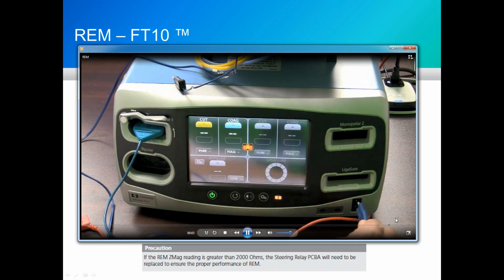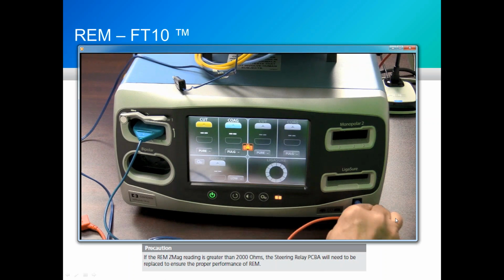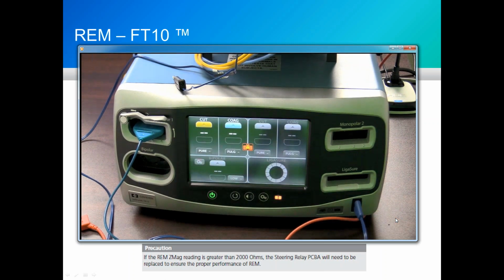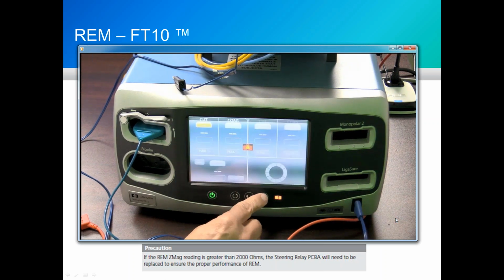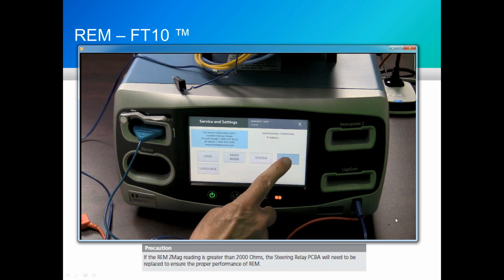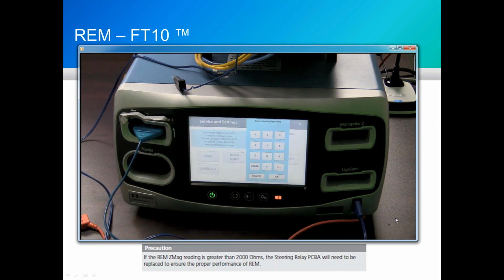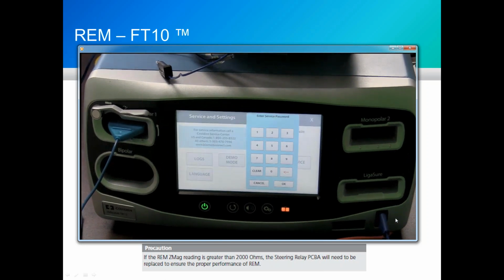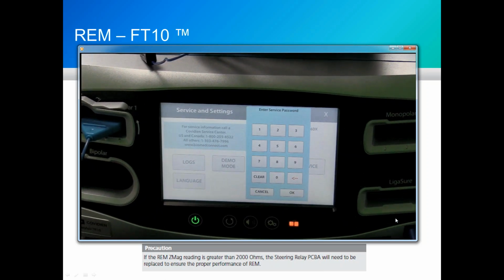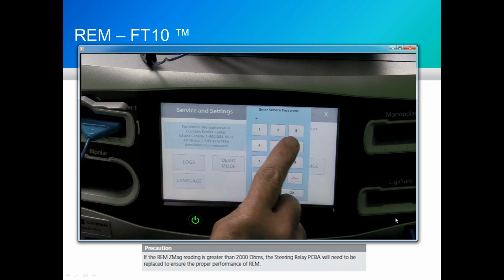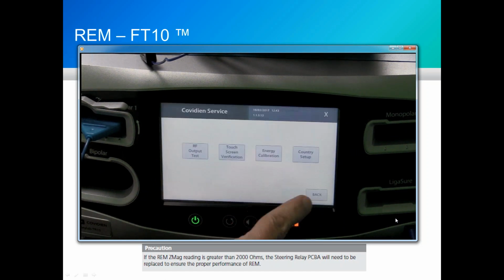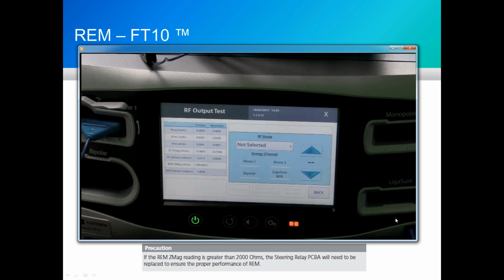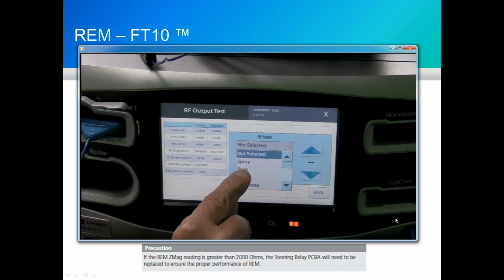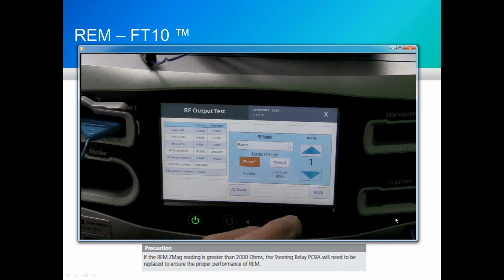So we're going to use a REM cable with the white plastic pin on the cable itself. You see me pressing the tools button, and we're going into service mode. We're going to enter the same password as we had on the Triad, which is 423213. RF output test. We're going to select pure for monopolar cut. Doesn't matter what our wattage is set for.